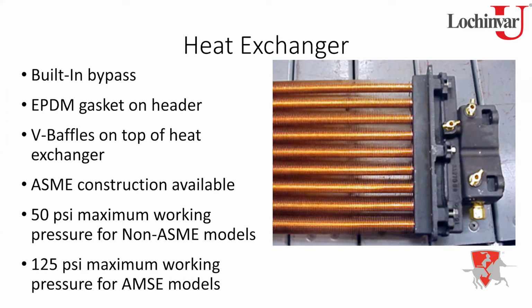A little bit about those copper tubes, though. They start out as a thicker copper tube, and we actually extrude those fins from that thicker copper tube. It thins out the inner wall of the copper tube, but those copper fins that you see on this heat exchanger give us a little bit more surface area so we can really pull the heat in from those burners and throw those BTUs in towards the water. So that's why you see that.